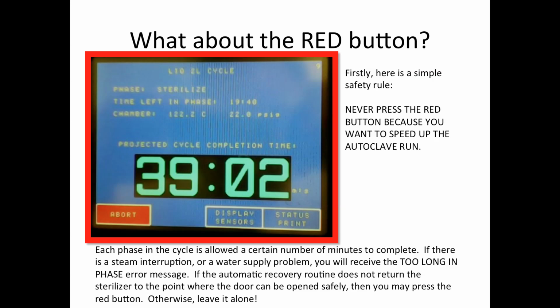Now, a question will come up, when do I use the red button? When do I press the abort button? First, here's a very simple safety rule. You never press the red button just because you want to advance the run, because it might be taking too long. The autoclave is automatically programmed to go through a shutdown and vent routine. So pressing the abort button is not going to move you along any faster.